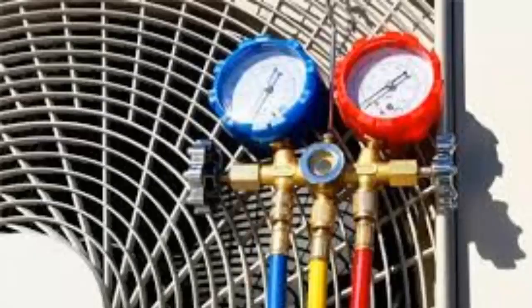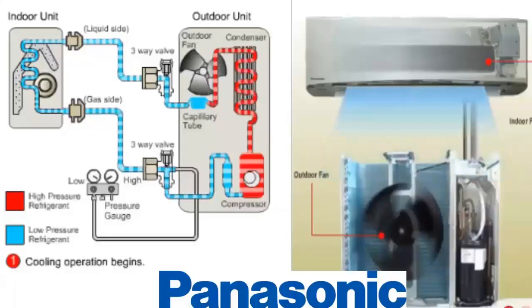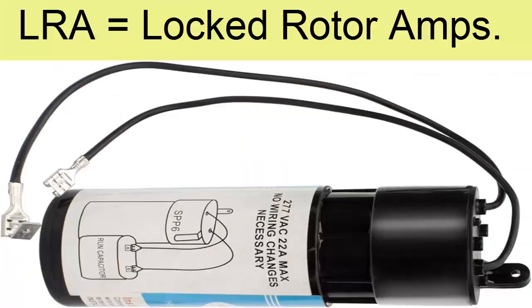6. Total refrigerant charge. Ensure that refrigerant has not been added unnecessarily due to confusing a capillary blockage with a real leak, as too much refrigerant can increase compressor pressure and amperage. 7. When the current value measured with the clamp does not exceed the LRA or startup current, but the equipment has trouble starting, you can try using a starting aid to potentially extend the life of the compressor.